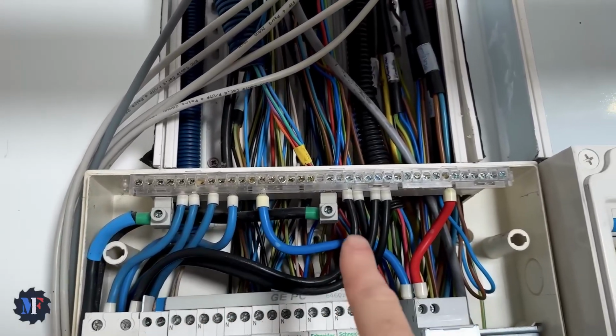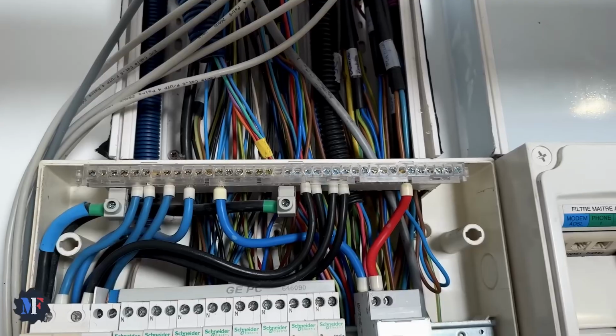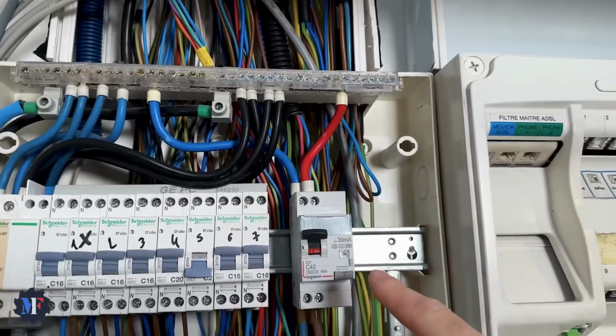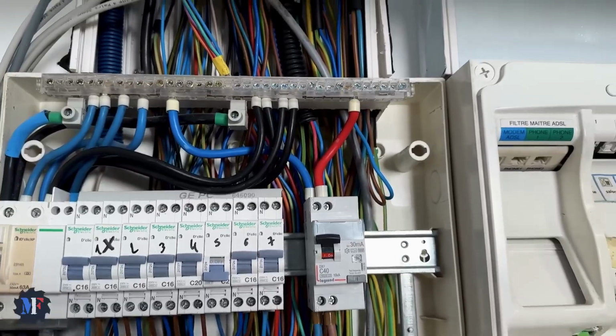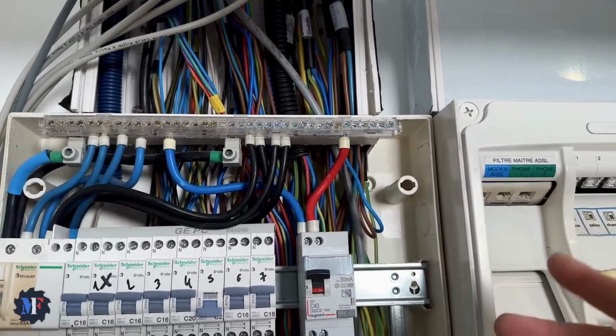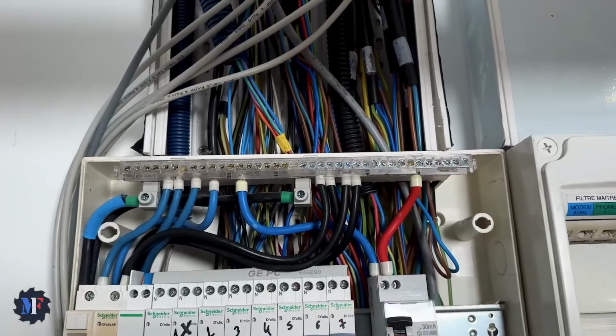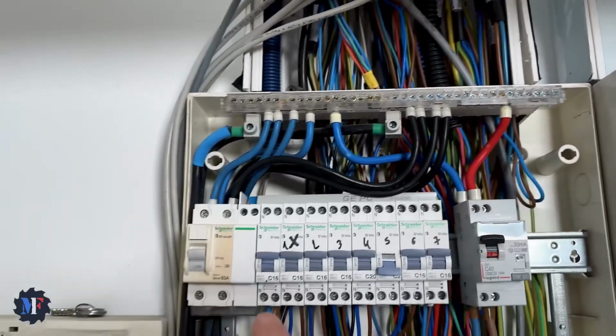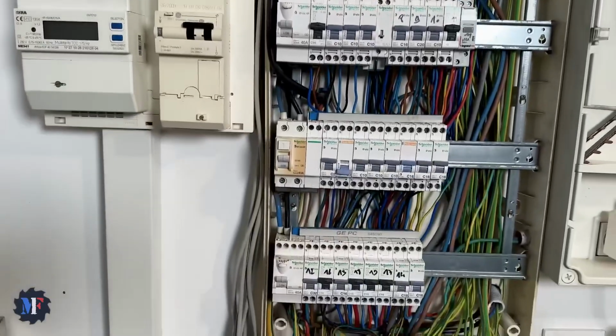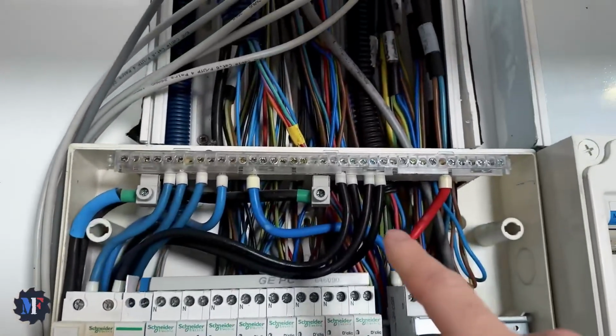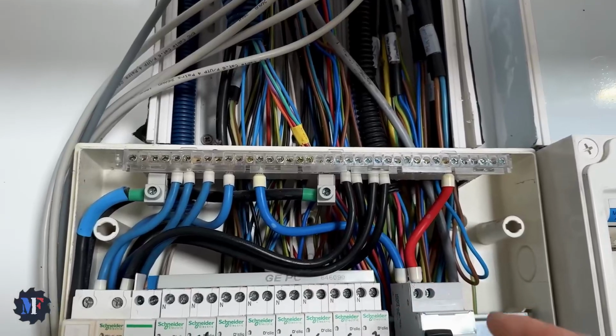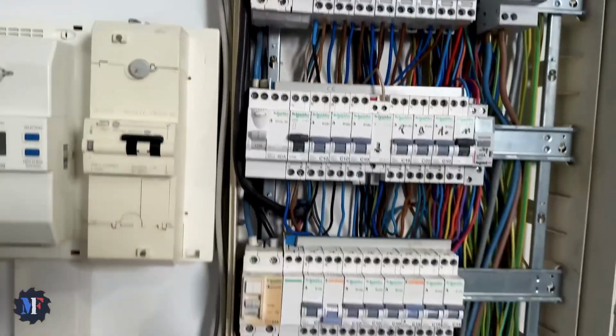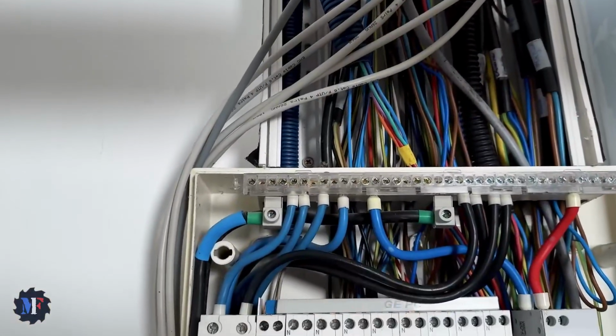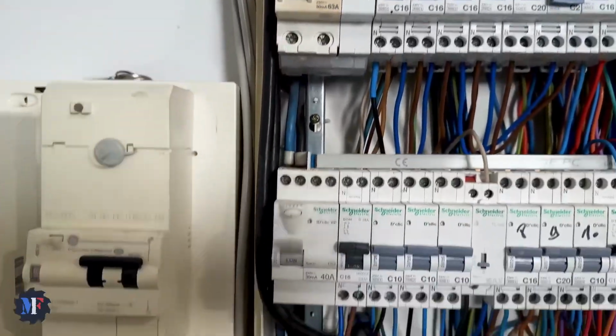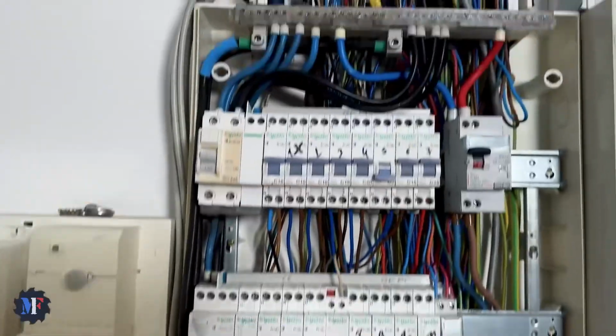The second one powers the phase terminal block here. The phase may be red, black, or brown. By the way, on my differential circuit breaker to supply the vehicle charging strip, I put it in red. It could have been brown or black. It doesn't matter. The neutral's on the terminal block, nice and blue, all good. So on this panel, I have 1, 2, 3, 4 differential switches, and you can see 1, 2, 3, 4 wires in 16 square millimeters, which supplies the phase. For all 4 differential switches, and it's the same for the neutral. I have 1, 2, 3, 4. We are indeed on each differential switch with the 16 square millimeter wire coming from the terminal block.